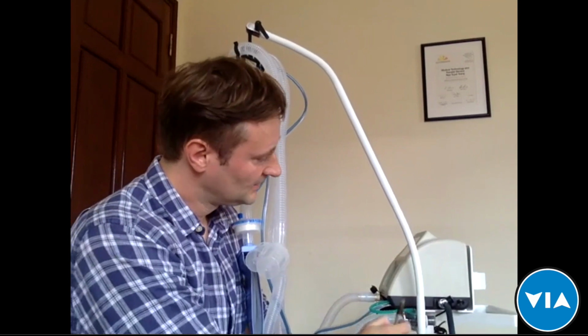All sources are okay. This is actually one of our differentiators against similar price point devices. They are limited by the input pressure. We have the oxygen port here, a standard DISS oxygen port that accepts up to 60 psi, and that means it can be used with wall oxygen and the cylinder, while many devices offered at this price point only accept up to 20 psi, which means they can work only with oxygen concentrators, which are much lower pressure devices. Ours accepts up to 60 psi, which means oxygen concentrators are fine with them as well. So all sorts of oxygen sources up to 60 psi, basically means in a medical ward, everything.